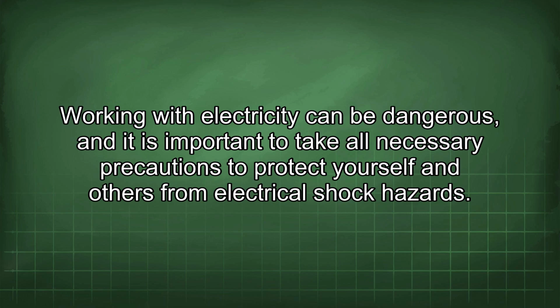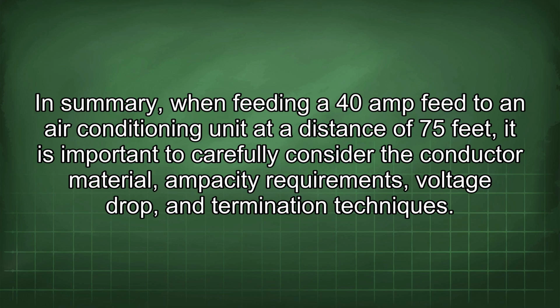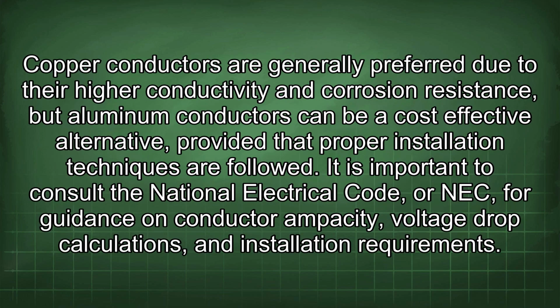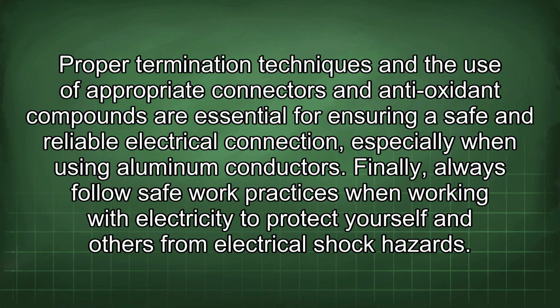from electrical shock hazards. In summary, when feeding a 40 amp feed to an air conditioning unit at a distance of 75 feet, it is important to carefully consider the conductor material, ampacity requirements, voltage drop, and termination techniques. Copper conductors are generally preferred due to their higher conductivity and corrosion resistance, but aluminum conductors can be a cost-effective alternative, provided that proper installation techniques are followed. It is important to consult the National Electrical Code, or NEC, for guidance on conductor ampacity, voltage drop calculations, and installation requirements. Proper termination techniques and the use of appropriate connectors and antioxidant compounds are essential for ensuring a safe and reliable electrical connection, especially when using aluminum conductors. Finally, always follow safe work practices when working with electricity to protect yourself and others from electrical shock hazards.